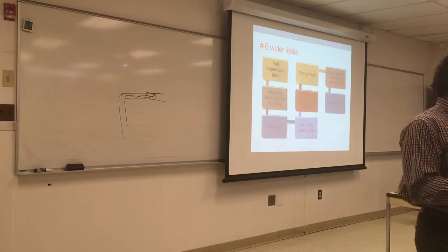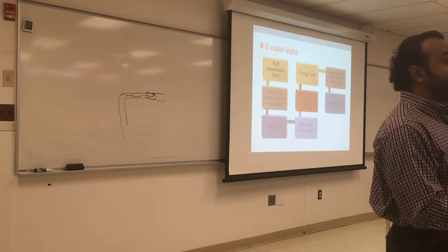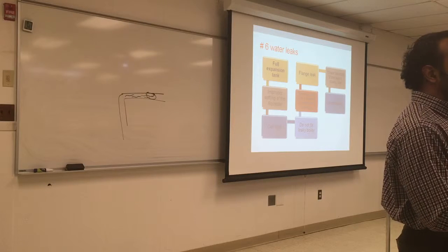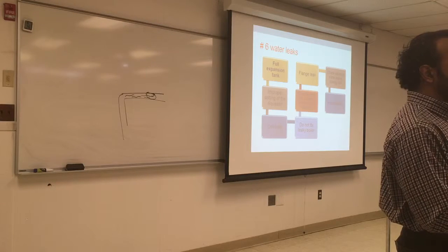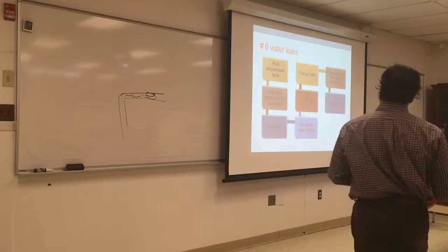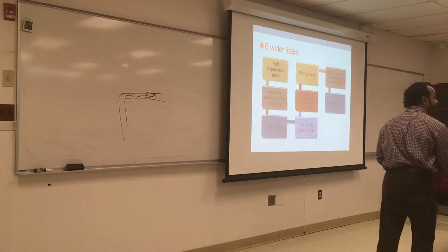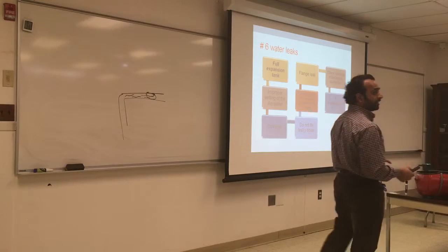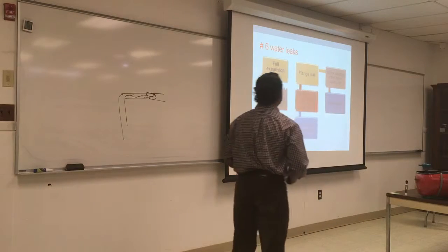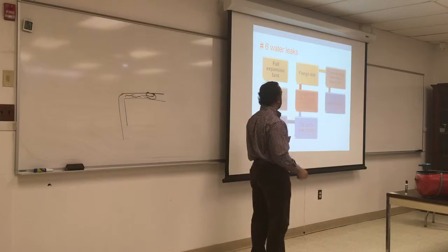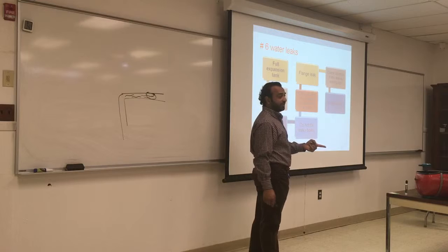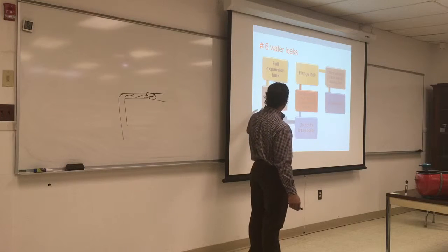What happens if you undersize it? It will leak. What happens if you oversize it? You do not have the right system pressure. The system will be under pressure. So you want to keep the system at the right pressure, and you don't want it to be too tight, so that when the water expands, it does not leak. So if the expansion tank is full, it means it's an undersized expansion tank.